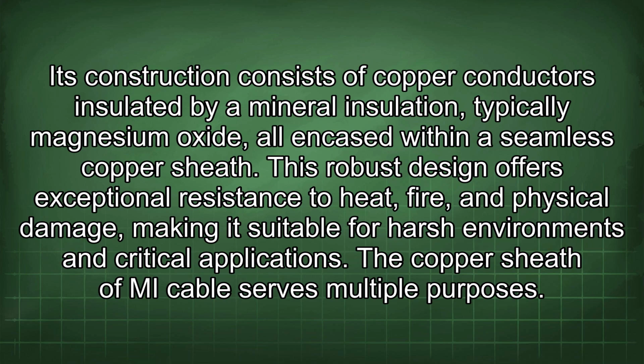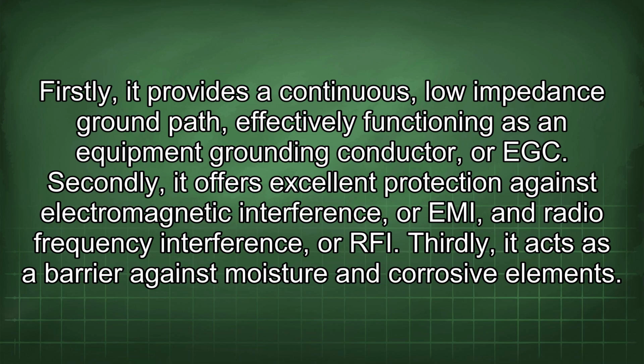The copper sheath of MI cable serves multiple purposes. Firstly, it provides a continuous, low-impedance ground path, effectively functioning as an equipment grounding conductor, or EGC.